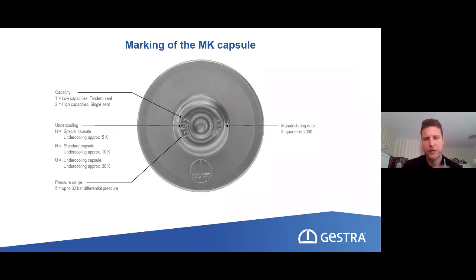If we take a look at such a membrane from above, then we can figure out a lot of information. The first letter that is stamped in here is 5, and this tells us something about the pressure range. So this capsule suits up to 32 bar differential pressure. And if the second letter is N, this is the standard capsule with the 10 Kelvin subcooling. But we could also have different kinds of capsules. Also an H is possible. Then we only have a subcooling of 5 Kelvin, so we are closer to the saturation curve. Or we could have a U, which means the undercooling capsule, then we are much farther away from the saturated steam curve, at 30 Kelvin.